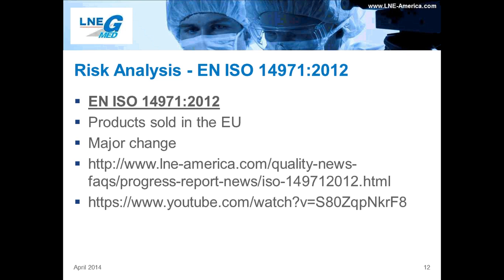For any products sold in the EU, now this is not just manufacturers located in the EU, for products sold in the EU, risk analysis should be performed according to the ISO 14971 revision 2012. Now there's been a lot of confusion because the normative text of the standard actually didn't change. However, the annexes of the standard introduced major changes that truthfully have just been overlooked by a lot of medical device manufacturers.